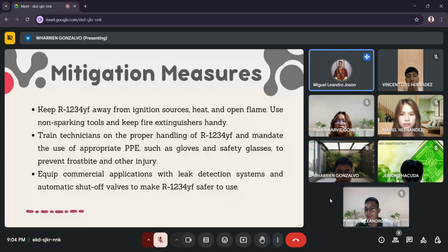Next, keep R1234yf away from ignition sources, heat, and open flame. Use non-sparking tools and keep fire extinguishers handy. Then, train technicians on the proper handling of R1234yf and mandate the use of appropriate PPE, such as gloves and safety glasses, to prevent frostbite and other injury. Lastly, equip commercial applications with leak detection systems and automatic shut-off valves to make R1234yf safer to use.